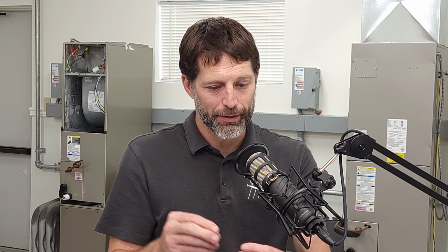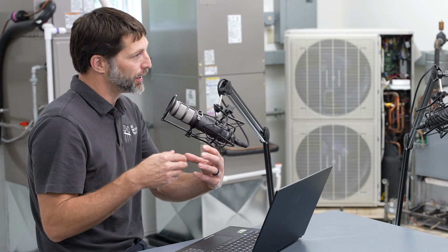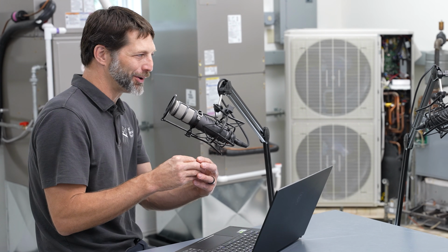Yeah. I mean, you could have larger tolerances, meaning like a large hole. Maybe it's a swage too big, or they're putting a copper pipe that's not the correct size onto a smaller one, and they're able to get away with it with the brazing. And you definitely can't get away with that when you're silver soldering. And you bring up a good point, Ty. A lot of the manufacturers are not silver soldering these evaporator coils together. They're just brazing them from the factory, and they use those braze rings a lot of the time in order to get a good joint.